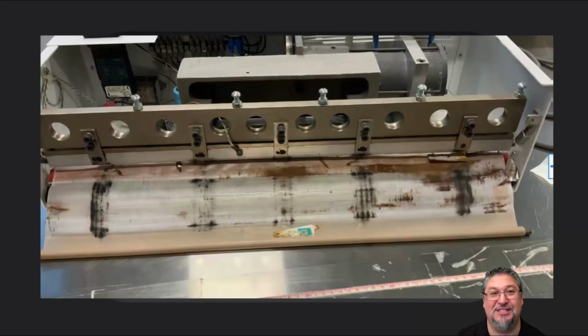We also have issues with our heat sealers, and you can see here, this is a heat sealer that has damage to it. The heat sealers, especially those bar ones where you lift it up and then it falls down, have a rolling mechanism inside that has to be rotated, because if you heat that same spot over and over and over again, eventually it will start to get worn out. There will start to be pieces missing. And you can see in this slide, hopefully you're able to see it clearly enough, that there are gaps in that heat seal. And when you look inside the heat sealer, sometimes you're going to see damage like this, where that same spot has been used over and over and over again. And now you have gaps in the heat sealer.